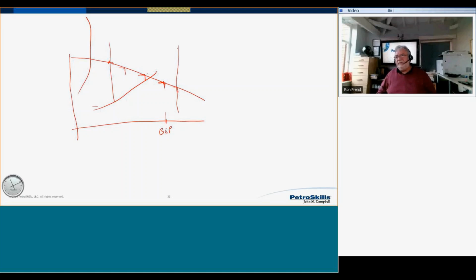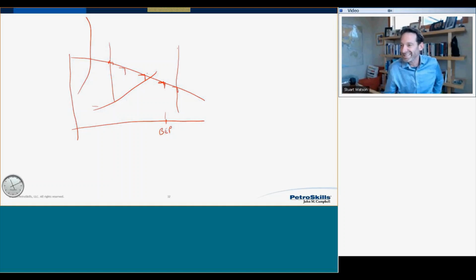So, Steve, what else have you got to say? Yeah, that's great, Ron. Thanks, mate. My early comment is this: the moment I see design margin and hydraulics, I always kind of freak out, because it's exactly that dialogue. Each time you add design margin, you change the pump curve, you increase the pump curve, and now you're not operating where you'd like to be operating, which is at your best efficiency point, because that gives you best reliability. So really, we aim for a design flow, and that design margin, there shouldn't be one.